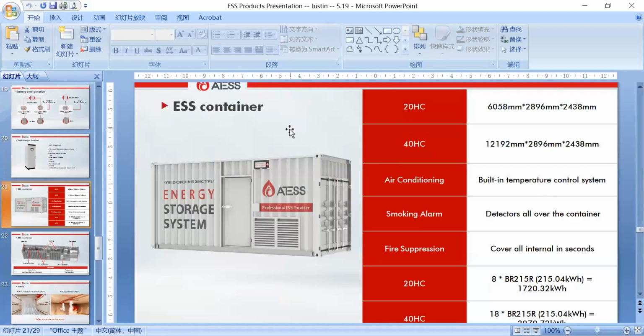Let's introduce our ESS container solution. ATESS has two containers, 20 high cube and 40 high cube, 20 feet and 40 feet. Here are the dimensions. What's inside our containers? Air conditioning to keep all the batteries at room temperature, 25 degrees. Smoke alarms and detectors all over the container, and fire suppression, because we need to take care of the fire.